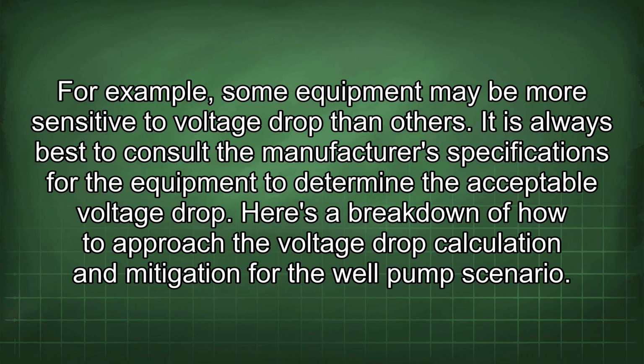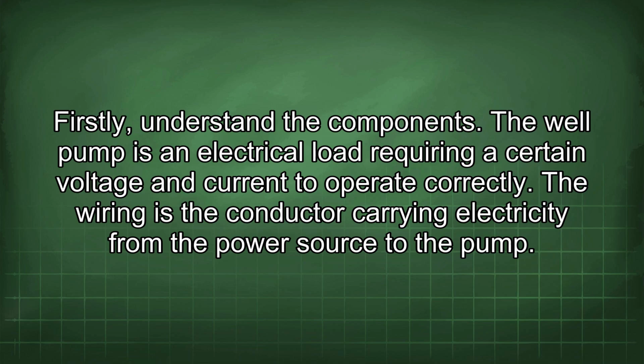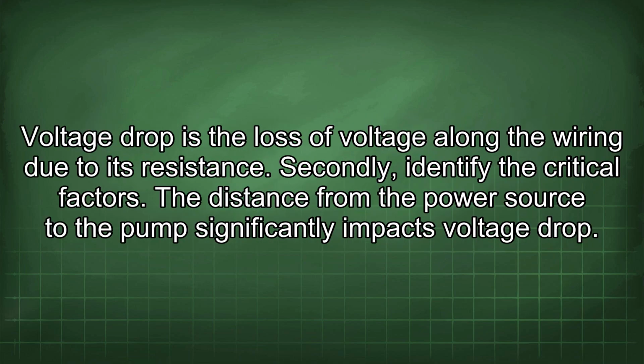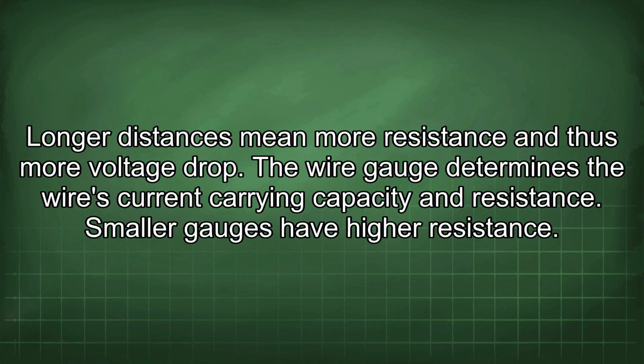Here's a breakdown of how to approach the voltage drop calculation and mitigation for the well pump scenario. Firstly, understand the components. The well pump is an electrical load requiring a certain voltage and current to operate correctly. The wiring is the conductor carrying electricity from the power source to the pump. Voltage drop is the loss of voltage along the wiring due to its resistance. Secondly, identify the critical factors. The distance from the power source to the pump significantly impacts voltage drop. Longer distances mean more resistance and thus more voltage drop.